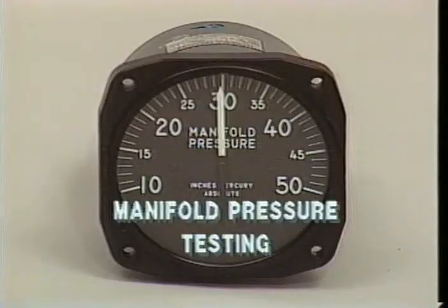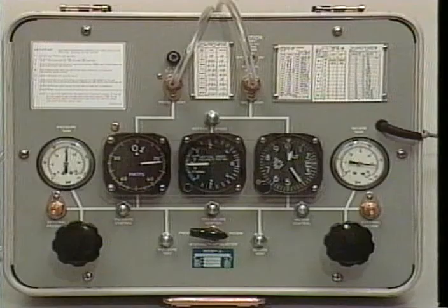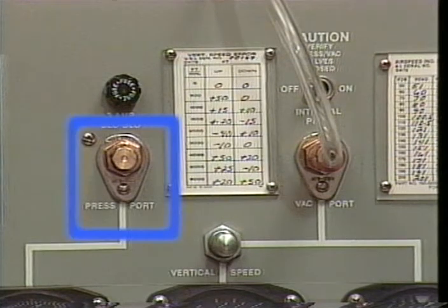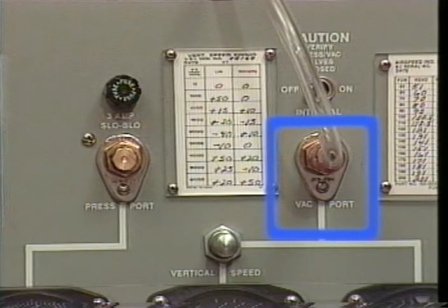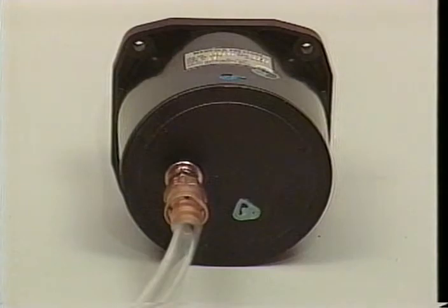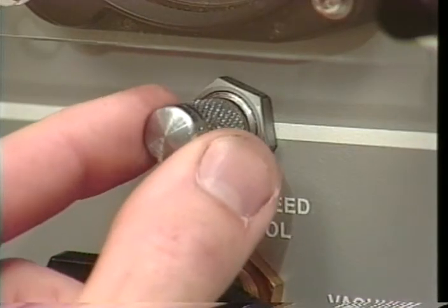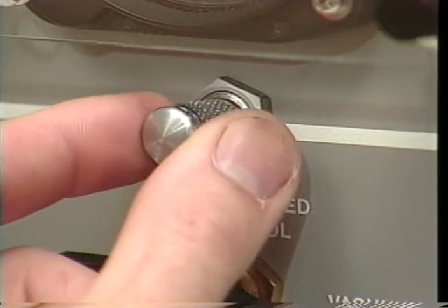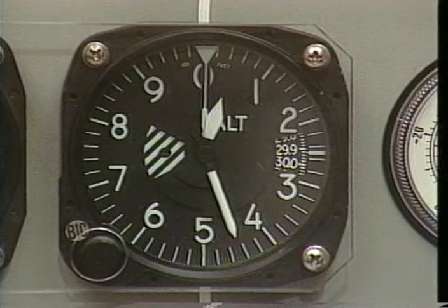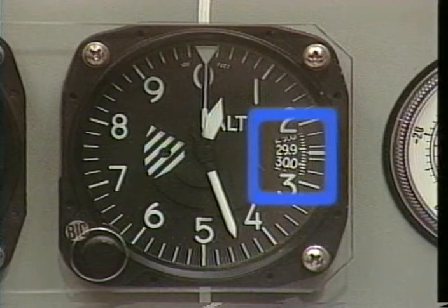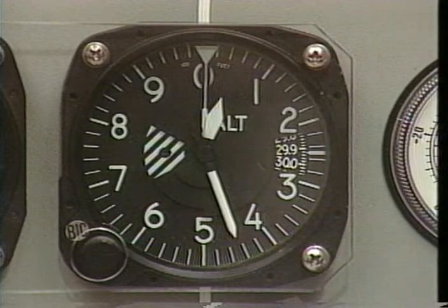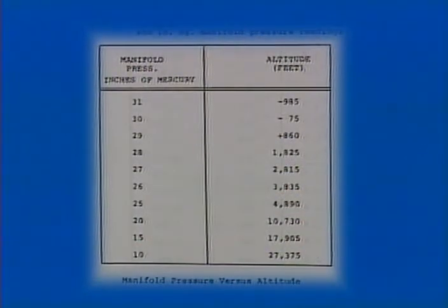Last, we'll test the manifold pressure gauge. Accomplish the preliminary setup procedure as previously detailed to ensure proper tester configuration. To begin the test, plug or cap the pressure port. Then connect the vacuum port to the manifold gauge you are testing. Next, open the crossbleed fully. Verify the altimeter is set to 29.92 inches of mercury. Refer to the chart in your maintenance manual or our tester manual for the equivalent altitude settings.